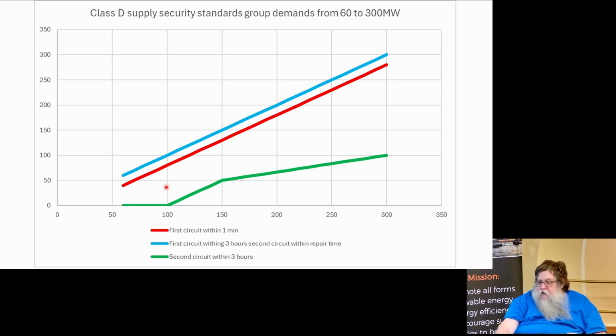So we've got the line where for a single circuit fault, everything must be restored in 3 hours. We've got the line where for a single circuit fault, we've got to keep everybody on except 20 megawatts. And then we've got this second circuit fault line here. And we don't have to get that back until 3 hours after the fault. So we could lose everybody for a second circuit fault and then get what was on the green line back. So it's still going to see an interruption.